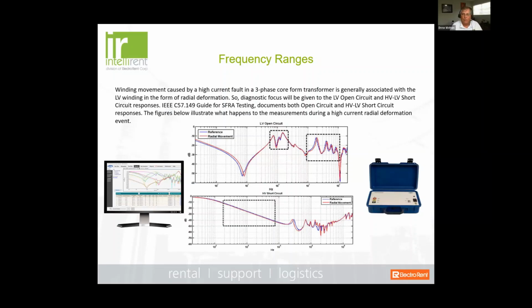Now, here's an interesting analysis, because remember, a number of things can cause physical displacement in the windings. It could be from seismic activity or moving the transformer from one location to another. But what we see is that winding movement that's typically caused by a high current through fault in a three-phase core form transformer is generally associated with the low voltage winding in the form of radial deformation. So your diagnostic focus will be given to the low voltage open circuit and high voltage to low voltage short circuit responses. And again, you can find all this information in C57-149. Okay, so open circuit and high voltage to low voltage short circuit responses are really where you're going to see an indication of possible damage caused by a through fault itself.